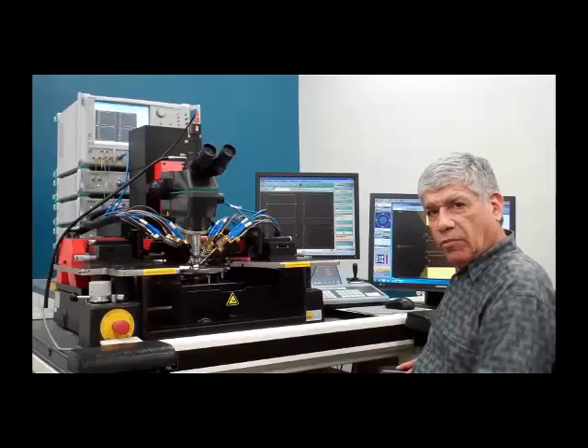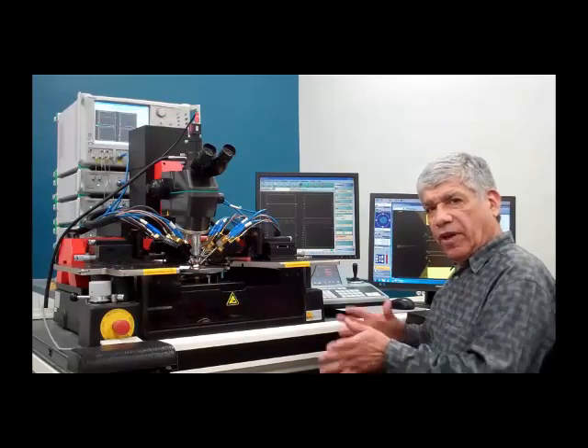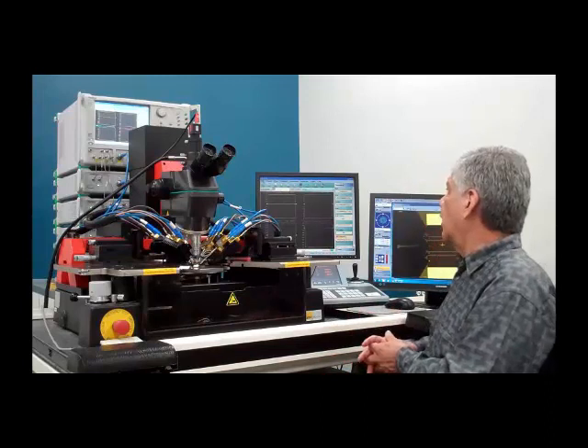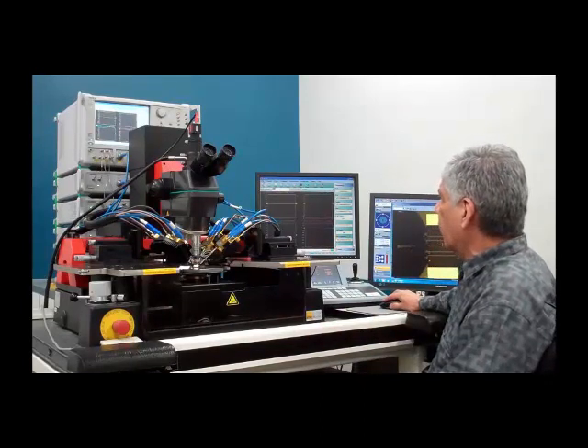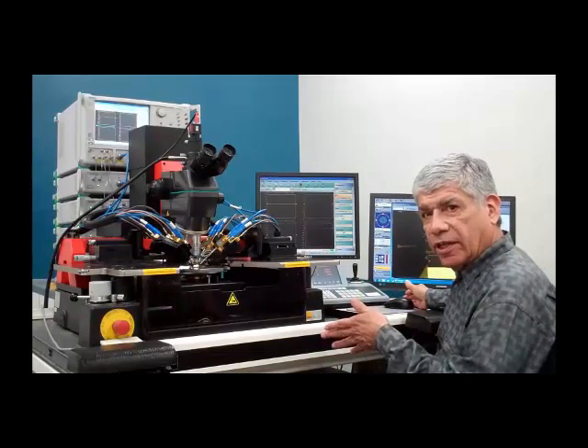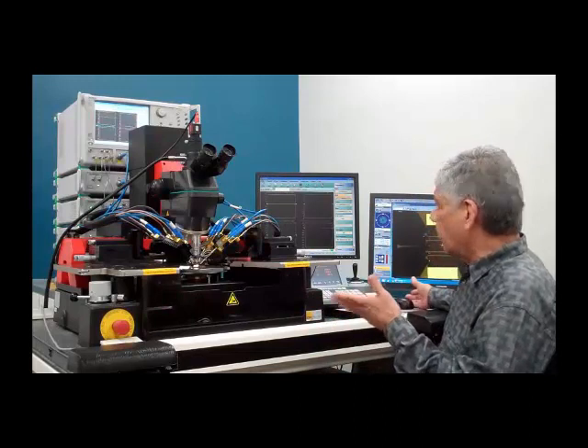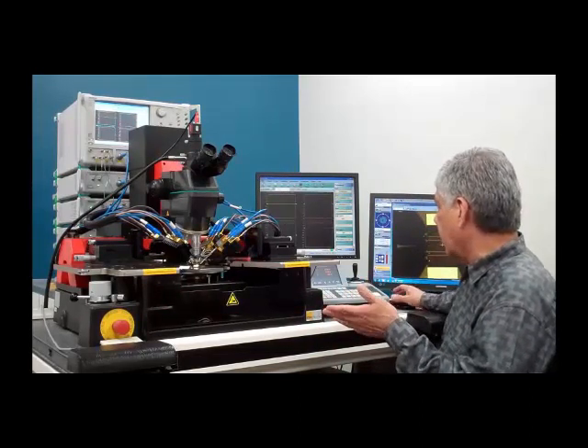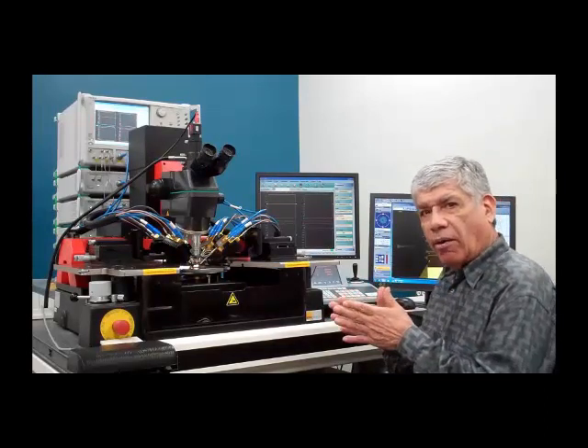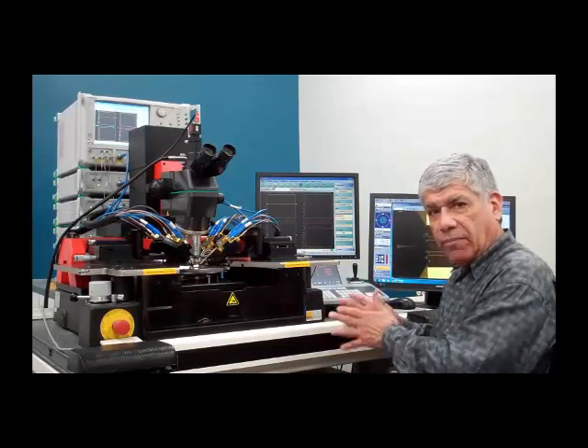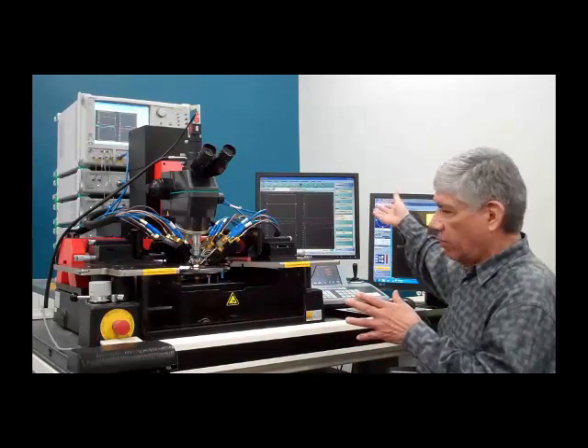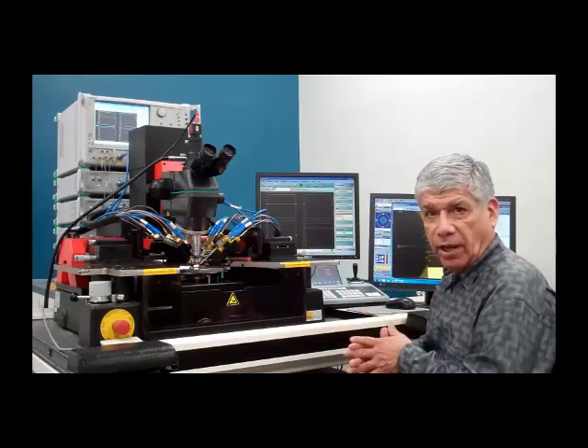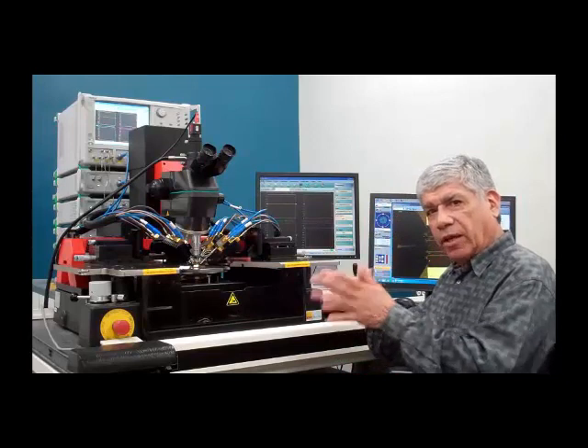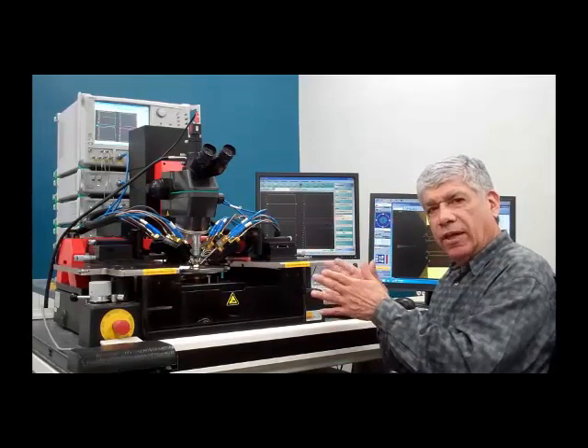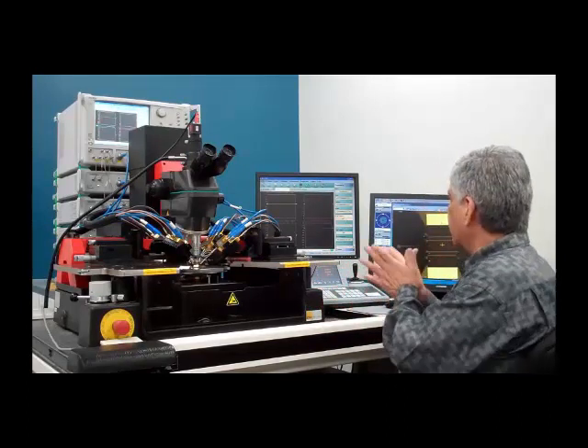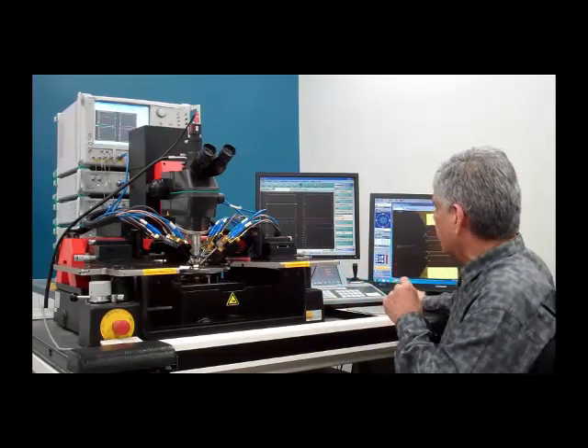So for setting up the system, we first want to go through the different parameters in order to configure it for the type of measurement we're going to be making. The good start point is going to be in frequency. So we'll set up our start-stop frequency. In this case, I've got 70 kilohertz to 145 gigahertz with 500 points. And if we wanted to concentrate our points in certain areas for the DUT measurement, we could switch from this linear display frequency sweep to a segmented sweep. In segmented sweep, we'll then be able to program specific frequency points, increase the number of points in certain areas, etc. So in this case, we'll just settle with the linear frequency sweep.